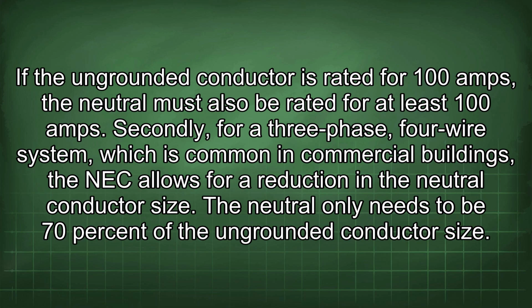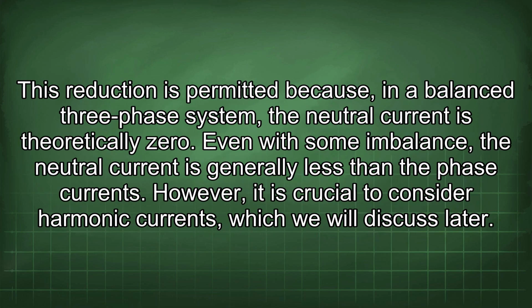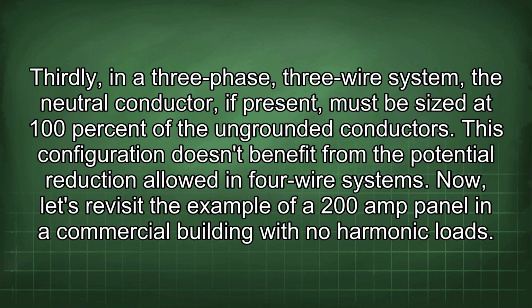Secondly, for a three-phase, four-wire system which is common in commercial buildings, the NEC allows for a reduction in the neutral conductor size. The neutral only needs to be 70% of the ungrounded conductor size. This reduction is permitted because, in a balanced three-phase system, the neutral current is theoretically zero. Even with some imbalance, the neutral current is generally less than the phase currents. However, it is crucial to consider harmonic currents, which we will discuss later. Thirdly, in a three-phase, three-wire system, the neutral conductor, if present, must be sized at 100% of the ungrounded conductors. This configuration doesn't benefit from the potential reduction allowed in four-wire systems.